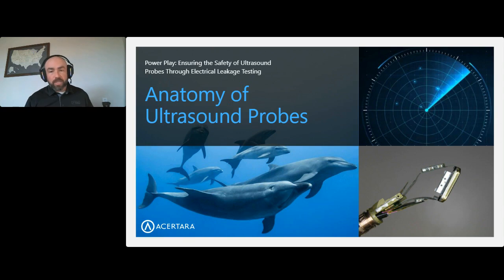So we've talked a bit about the anatomy of ultrasound probes. The image that you're looking at here is actually an exposed ultrasound array. On the right is the array, and we're looking at it from the side. Sometimes those arrays actually have connectors on them, and the connector maybe plugs into a flex circuit that has all the wires soldered into it, and that gets plugged into the array, and that's all inside of that control housing.